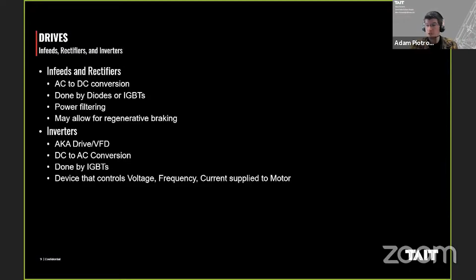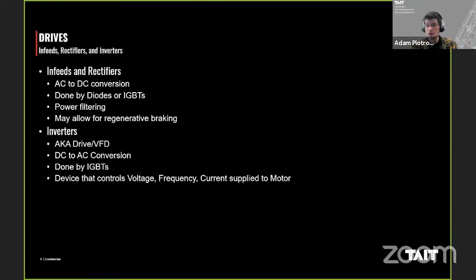Whereas the inverter is going to do the DC to AC conversion. This is how you can spin a motor at half speed, 30 hertz instead of 60 hertz. The inverter is essentially reconfiguring the three-phase voltage that you would get straight from a utility by converting it to DC and then reforming it into AC on the opposite side. This device controls the voltage, frequency, and current supplied to the motor so that we can control speed, control current, and ensure that we follow our position demand as we are queuing it from the front end, to make sure it's doing what it's supposed to be doing.